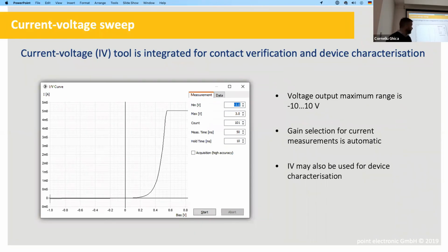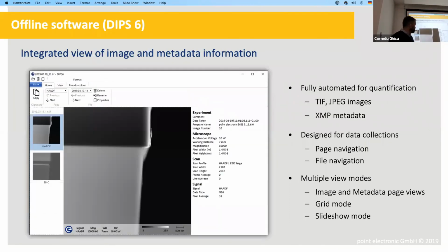And this is used in several aspects. In situ, as I covered, the other aspect is used to make sure that the device is alive when you start your experiment. It wasn't damaged during preparation. And another reason to use it is to monitor the reverse bias zone to see if the leakage current is increasing over time. That would be a signal of beam damage to the device. And those are several reasons why we had to integrate this into our electronics as well.